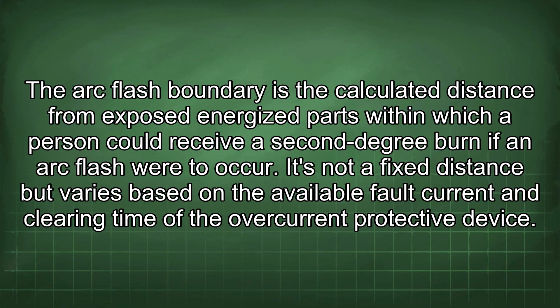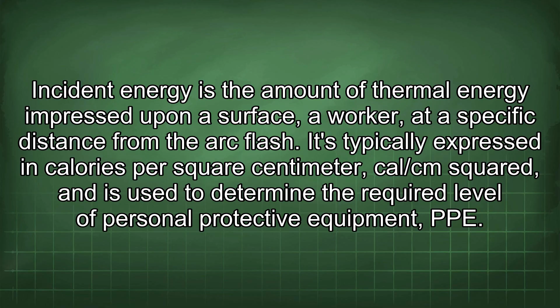device. Incident energy is the amount of thermal energy impressed upon a surface, a worker, at a specific distance from the arc flash. It's typically expressed in calories per square centimeter, cal/cm², and is used to determine the required level of personal protective equipment (PPE).